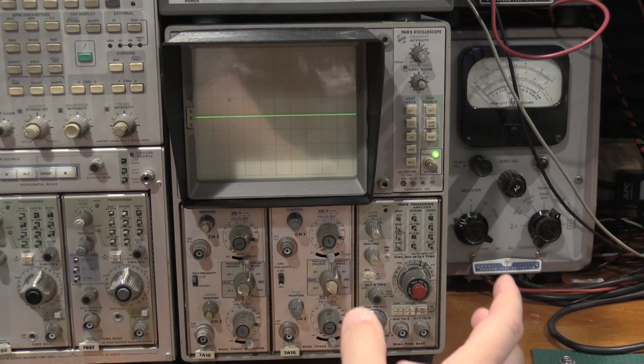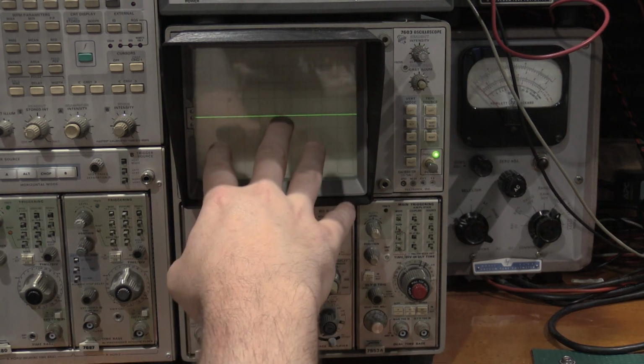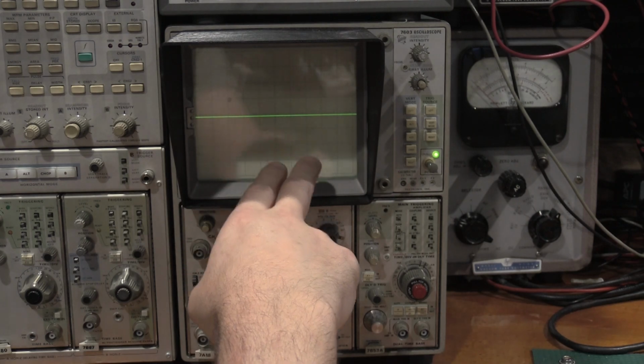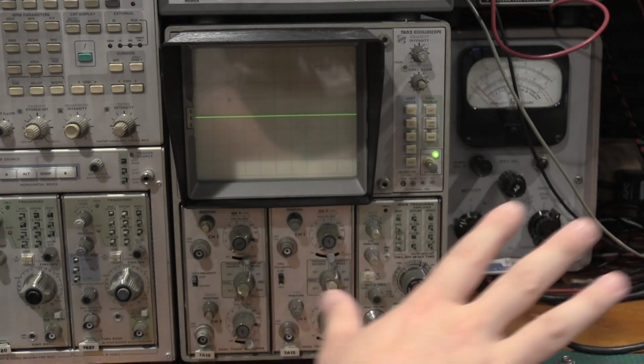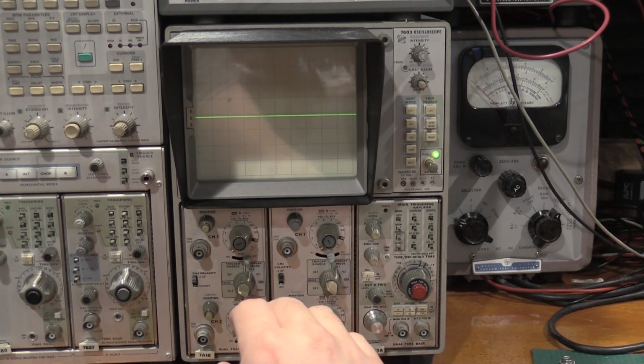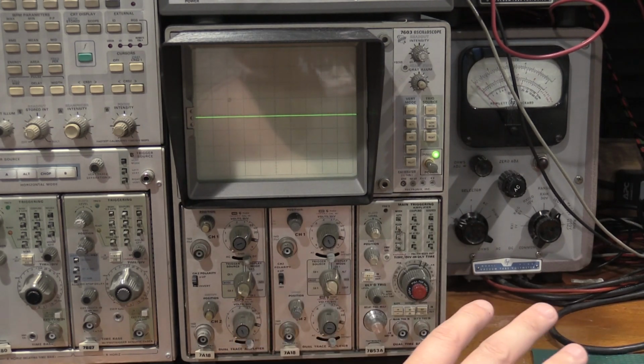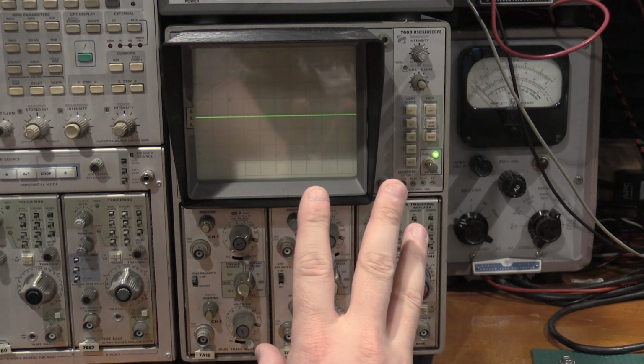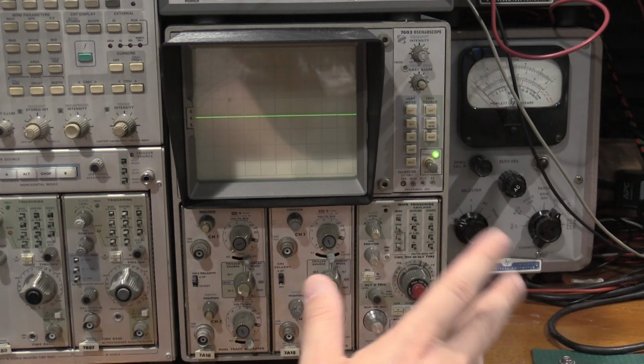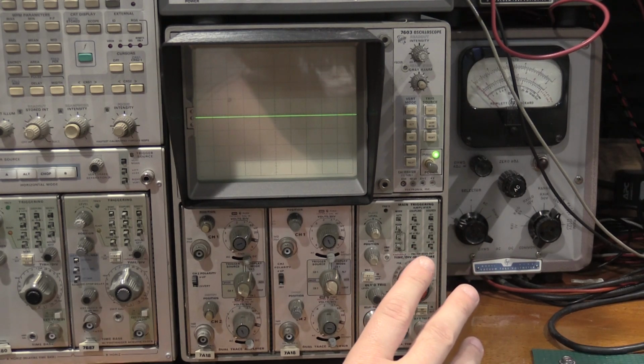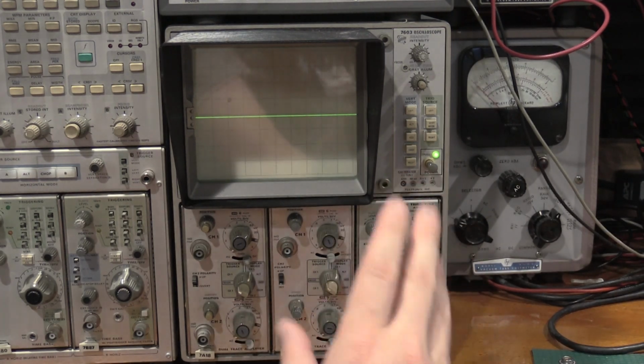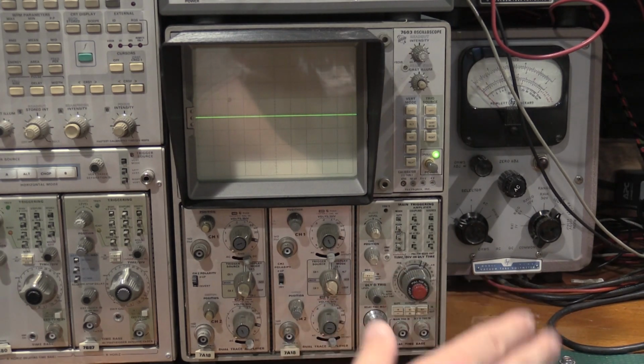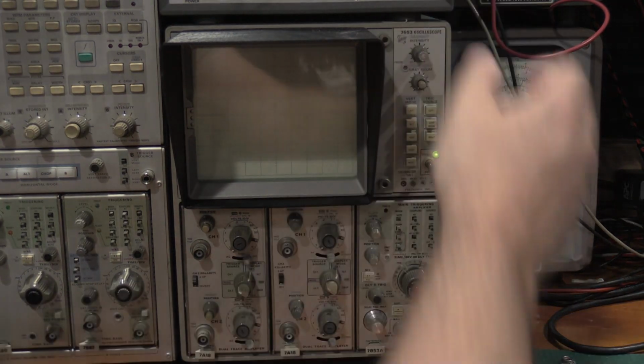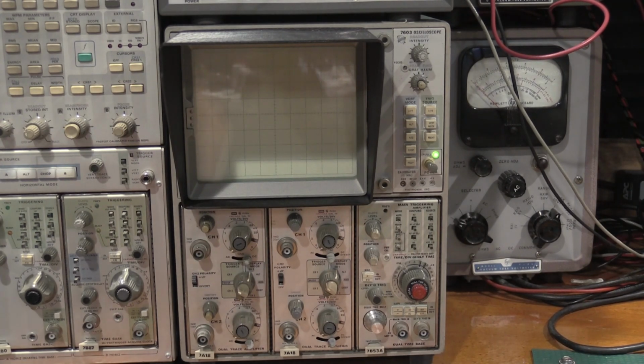What you're looking for is called double peaking. What happens is if the trace gets brighter and then dims out and then gets brighter again, stop troubleshooting the scope. It's a high-hour tube. You're either going to need to source a tube or it's a parts unit. There's a lot of speculation on why the double peaking occurs. However, it is terminal to the tube. There is no fixing it. Now, on a 400 series scope, it's relatively easy to find a tube.